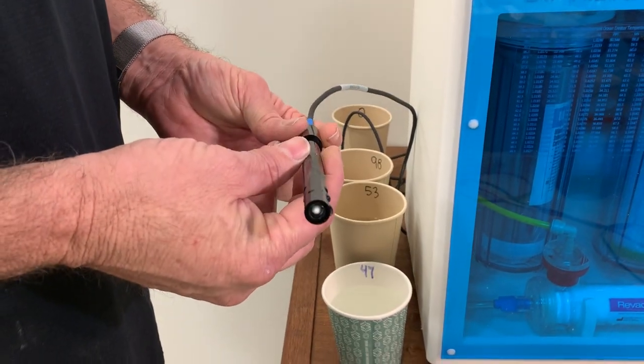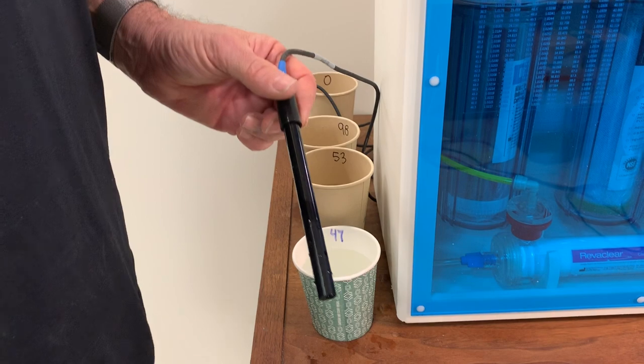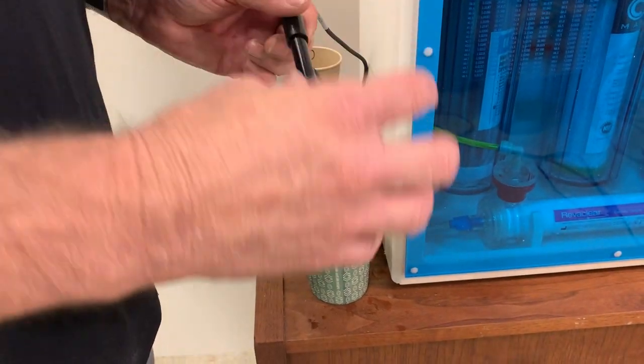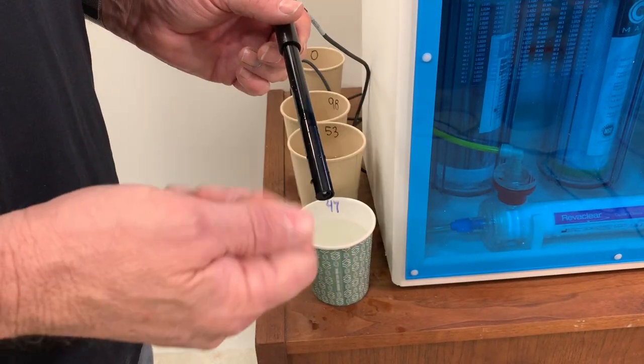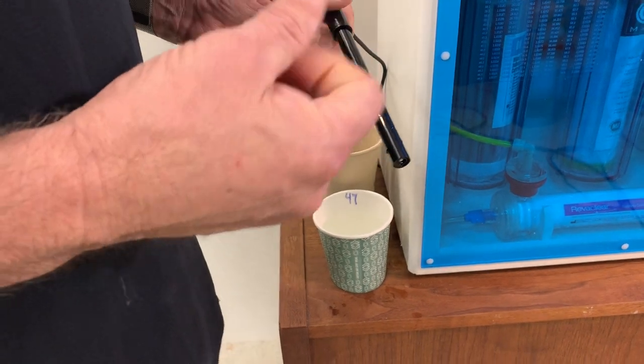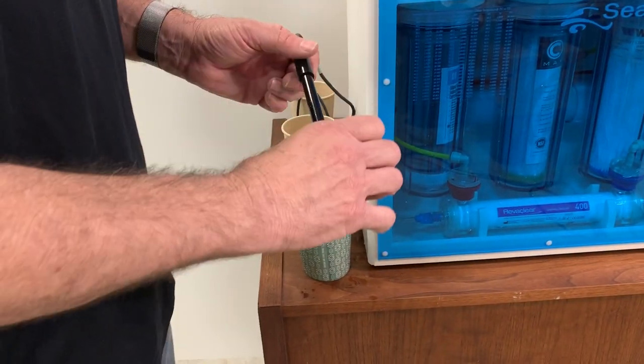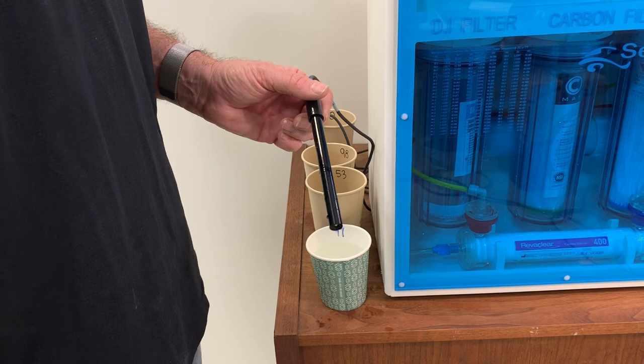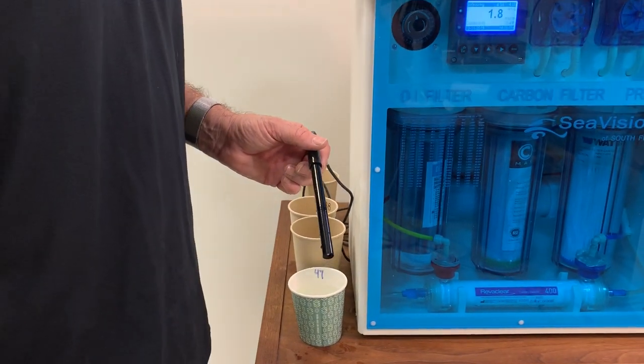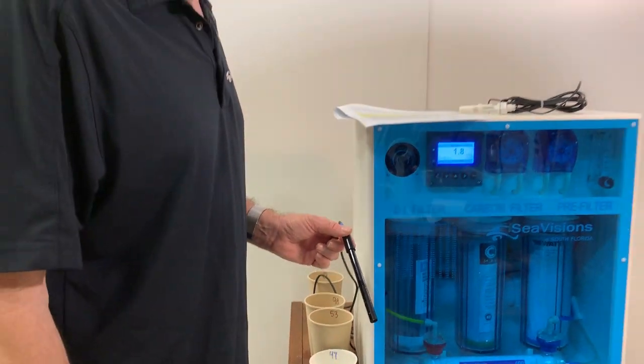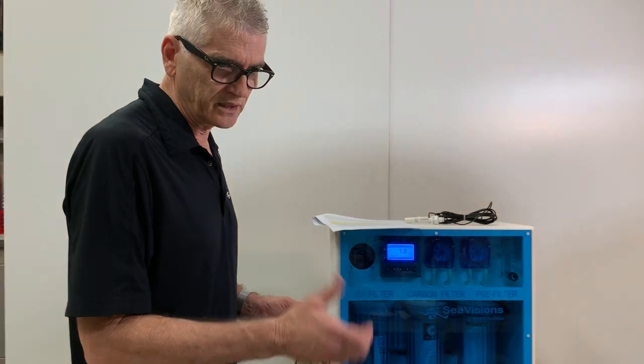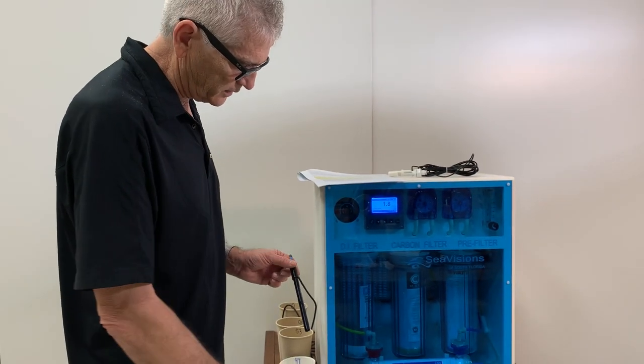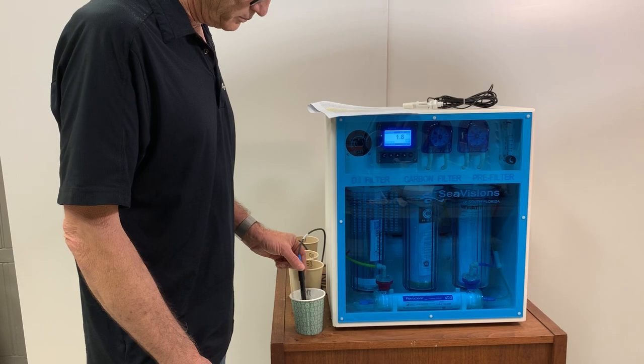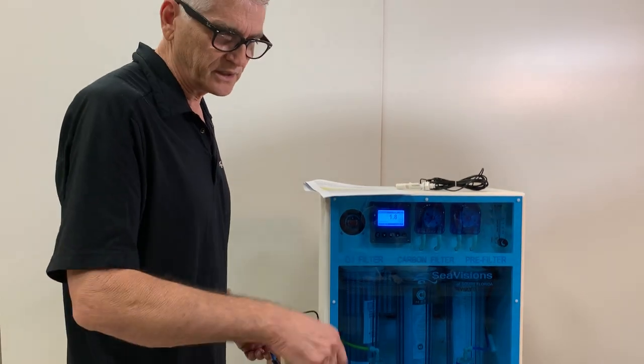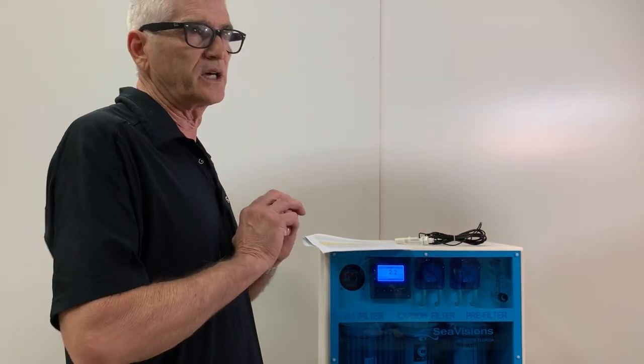It's very delicate. It cannot be dropped. If it gets detritus or salt or something encrusted on it, it is not going to read correctly, and you're going to be wondering, what the heck do I do? Generally, all you do is, I take a lemon myself and I cut the lemon, I squeeze the lemon into a cup, I put the probe into straight lemon juice and I swirl it around, and that lemon, believe it or not, will remove most everything on that probe.